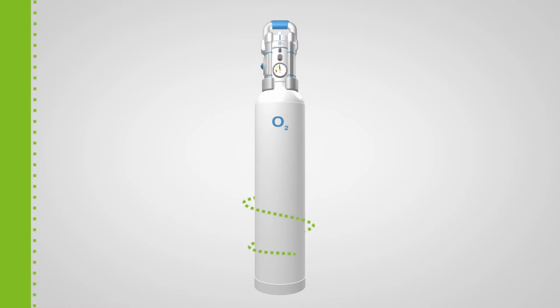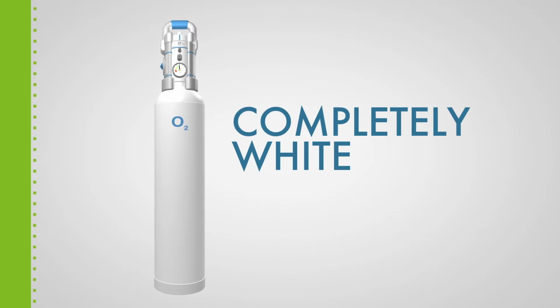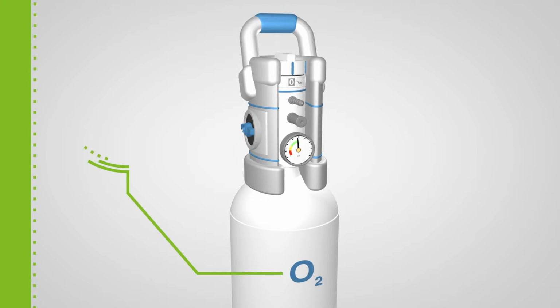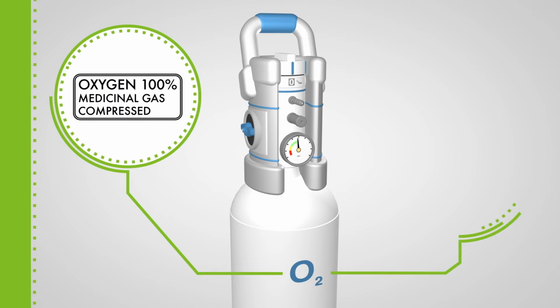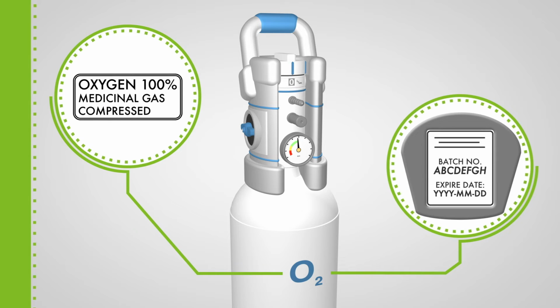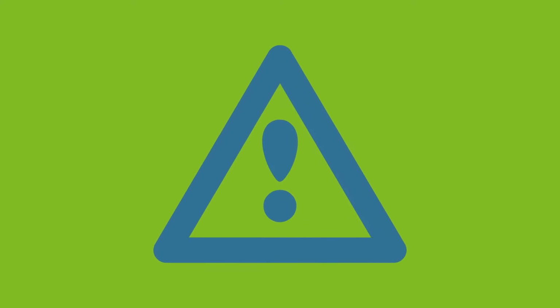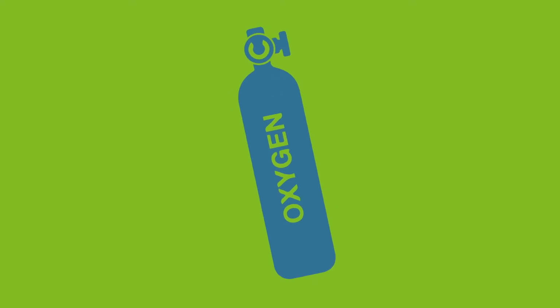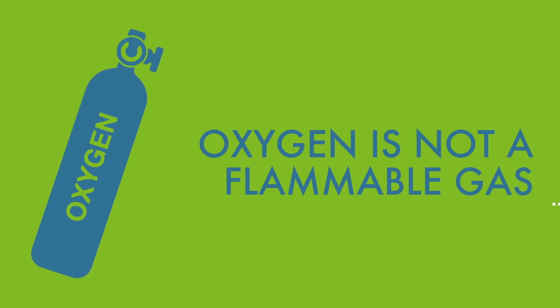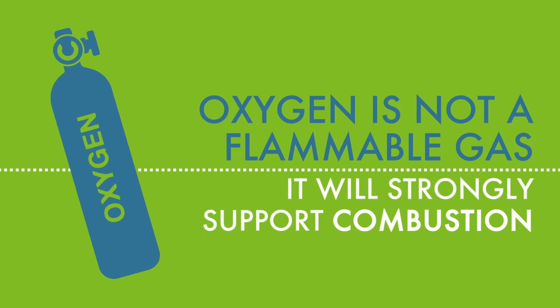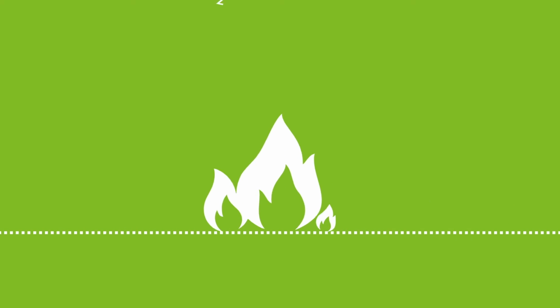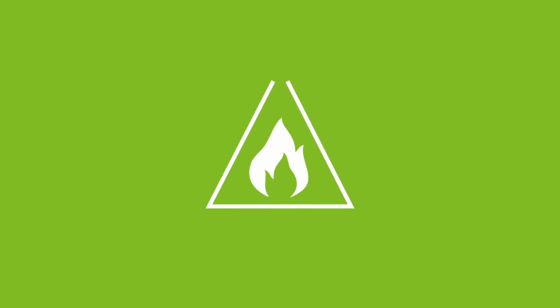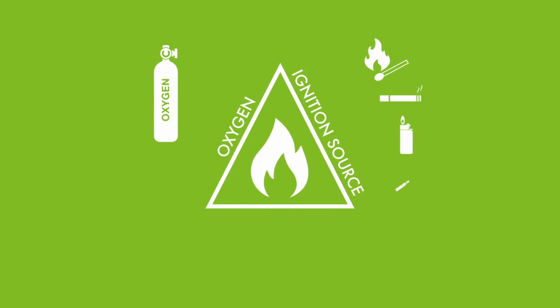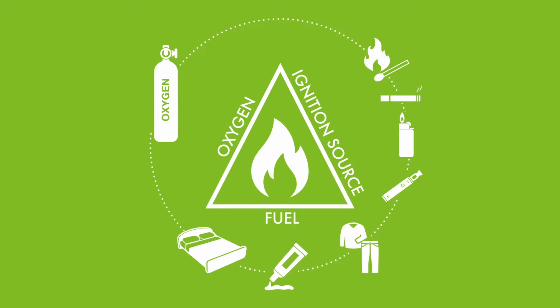Remember that medical oxygen cylinders are completely white, are fitted with a label stating that it is medical oxygen, and should be used within their expiry date. Before talking about the operation of the valve, remember that although oxygen is not a flammable gas, it will strongly support combustion. Things that don't normally catch fire in air will burn violently in oxygen. So you need to keep the oxygen away from sources of ignition such as flames, stoves, lighters, and smoking materials.